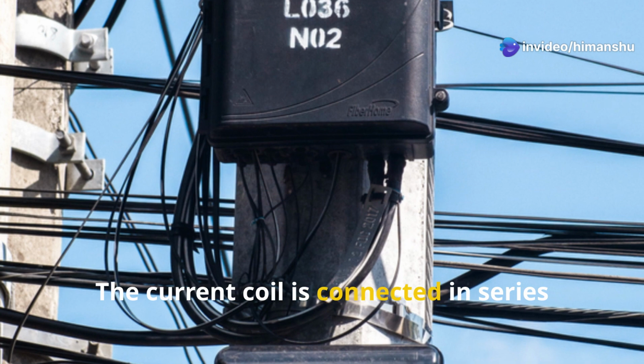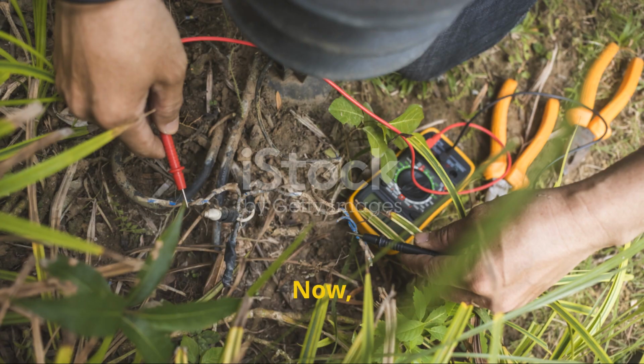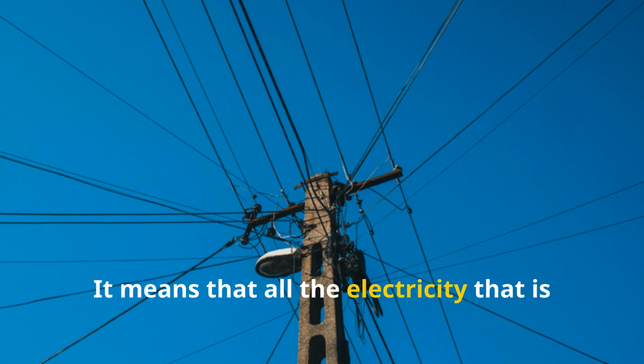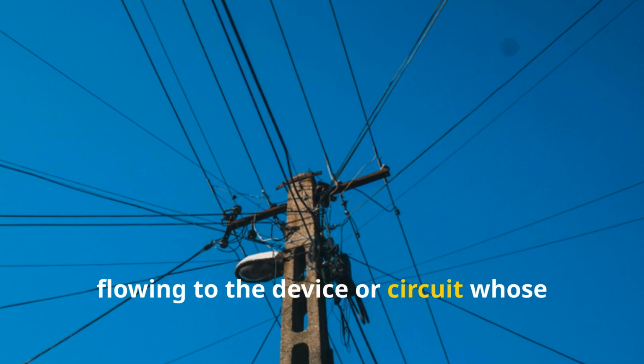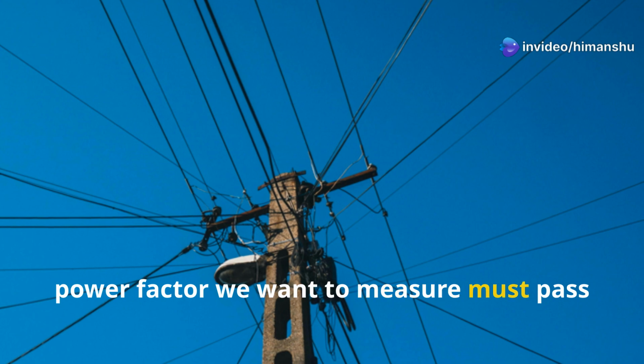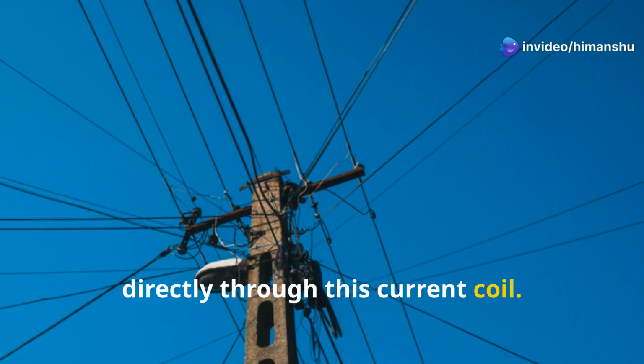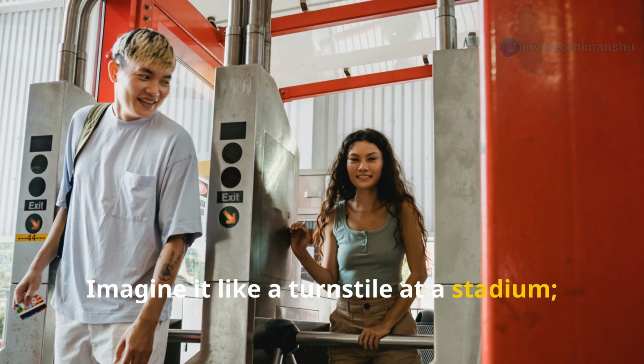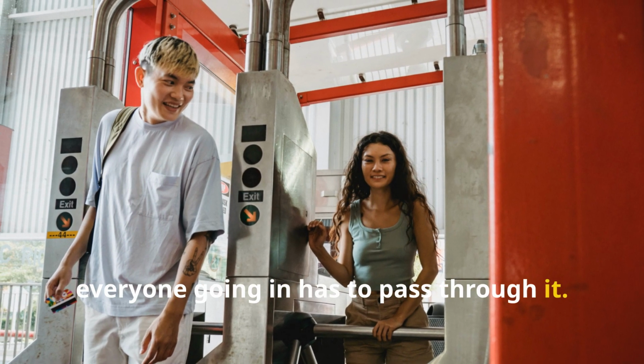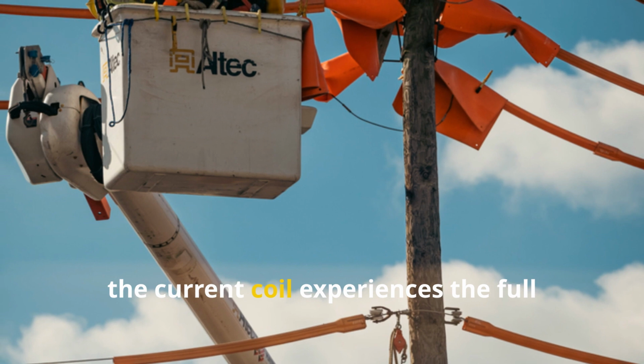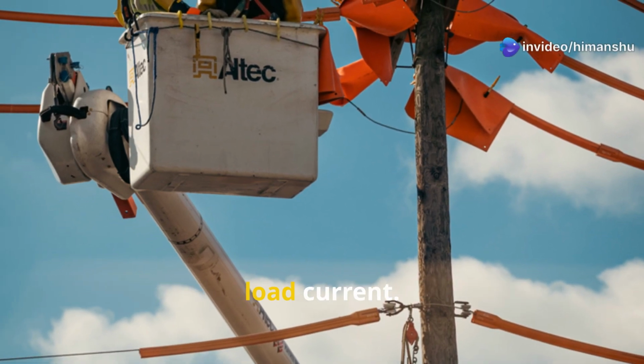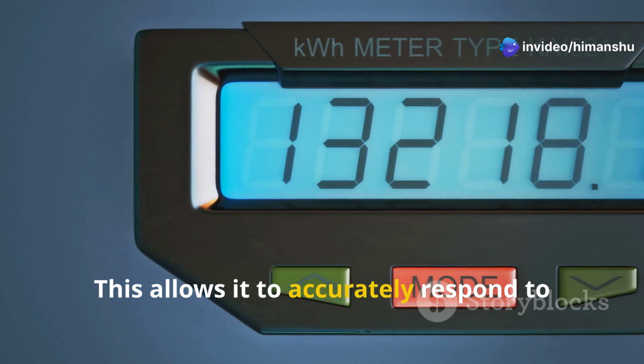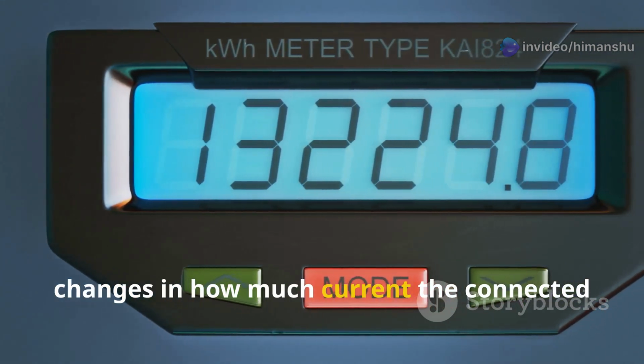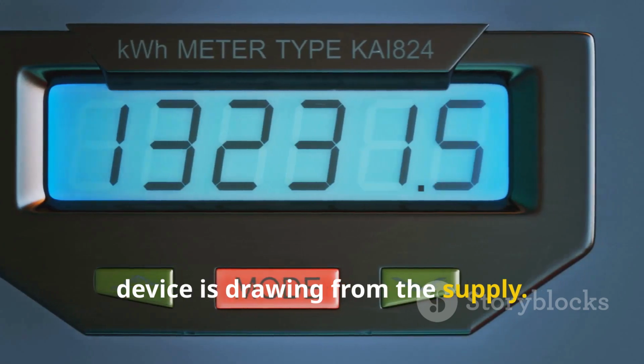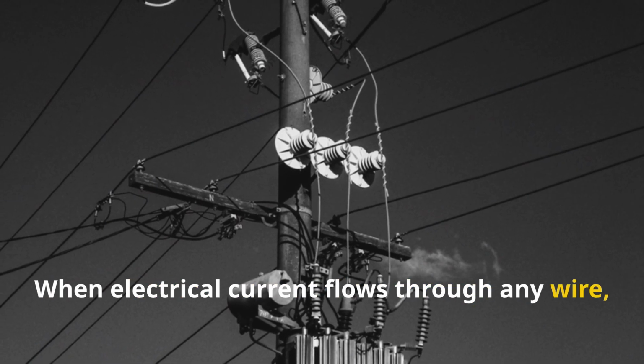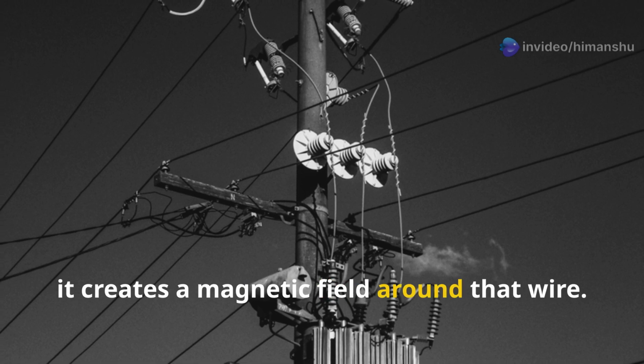The current coil is connected in series with the load. Now, what does in series mean? It means that all the electricity flowing to the device or circuit whose power factor we want to measure must pass directly through this current coil. Imagine it like a turnstile at a stadium, everyone going in has to pass through it. Because it's in series, the current coil experiences the full load current. This allows it to accurately respond to changes in how much current the connected device is drawing from the supply. When electrical current flows through any wire, it creates a magnetic field around that wire.